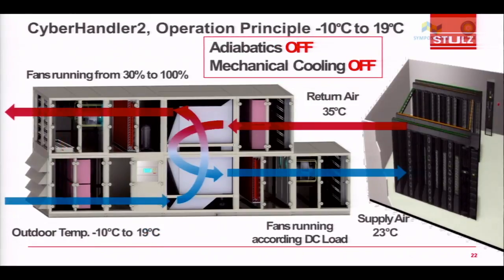Now here is our condition. Now you see the minus 10 to 19 degrees Celsius. In this range, you are still not running your compressor. You are achieving the cooling by means of outdoor air, not even with adiabatics getting on, and still your supply temperature is maintained at 23 degrees Celsius. Only the deployment of these projects has to be customized and worked in accordance with the site location. How to locate the air handling unit, your data center position is very, very important.